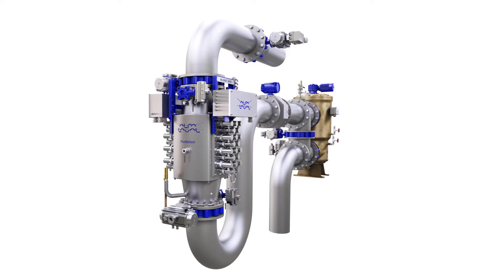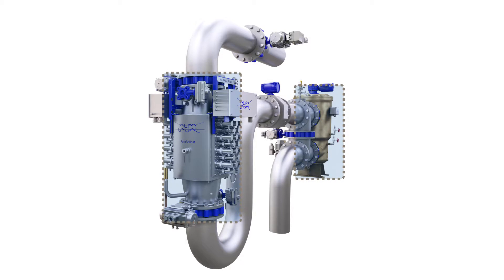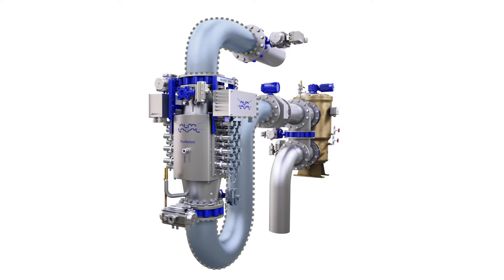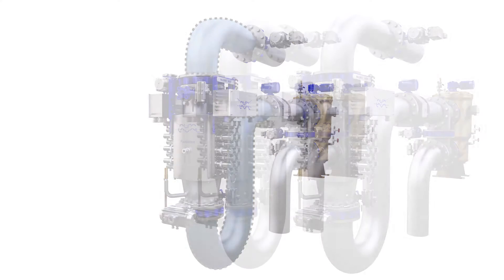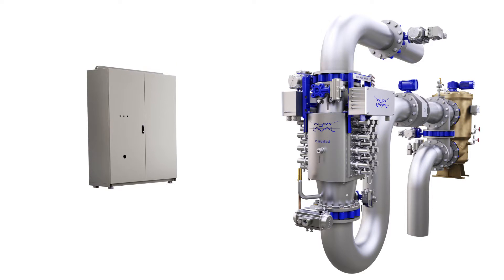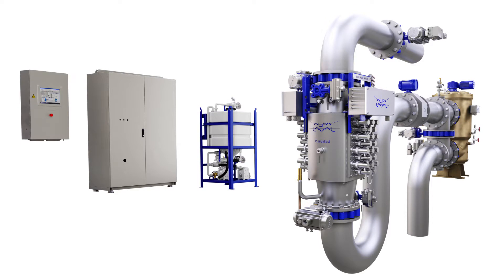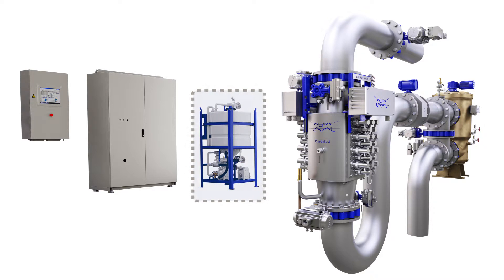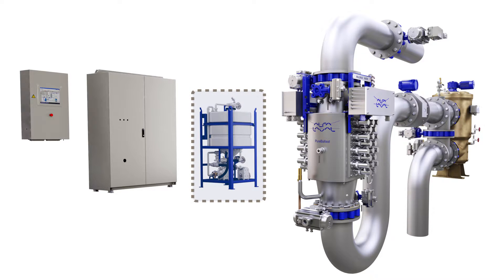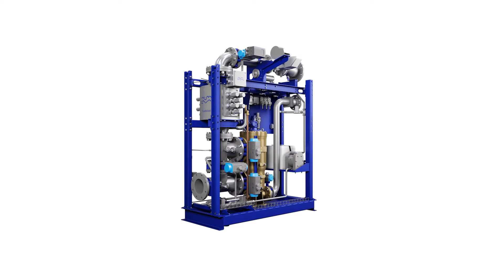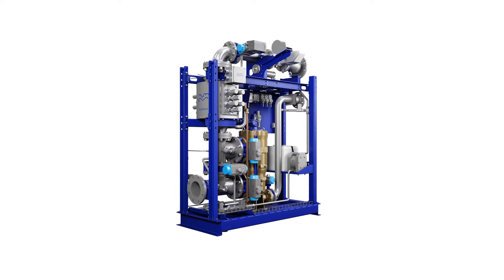Pure Ballast 3.1 is modular. It consists of a filter stage and a reactor stage, integrated into the ballast water piping as in-line components. A few freely placed components support the in-line system, such as an automatic cleaning-in-place unit to prevent any UV-impairing buildup. For smaller vessels, there are also skid-based plug-and-play solutions.